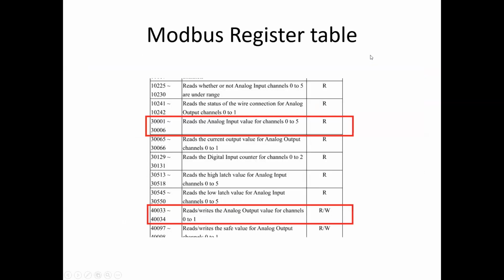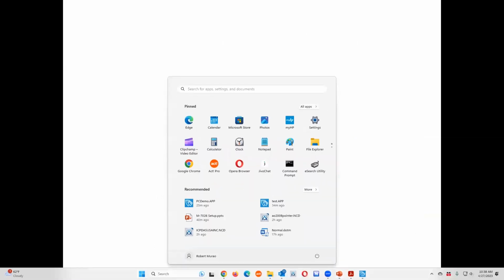Let's see, this is the Modbus register table. This is the second piece of information you need for the individual devices. This is for the M7026. So again, this one had 2 analog output channels, which are registers 40,033 and 40,034. And then the analog input registers, it has 6 of them labeled channels 0 through 5, and the Modbus addresses associated with those are 30,001 through 30,006. To bring this all together, let me just go back to AVEVA Edge and show you, well, actually, let me show you this first.